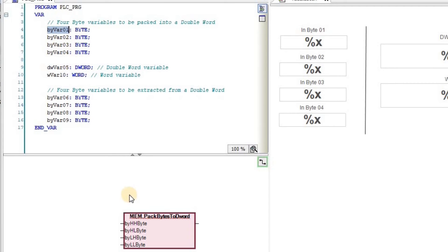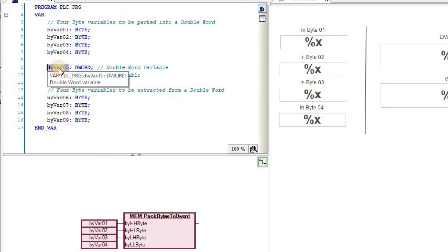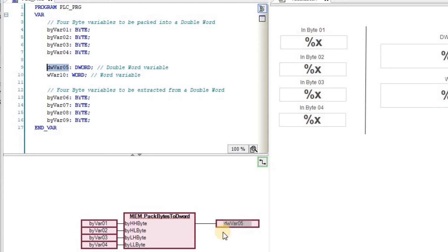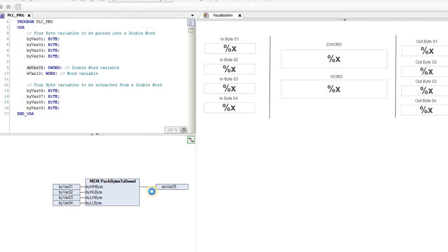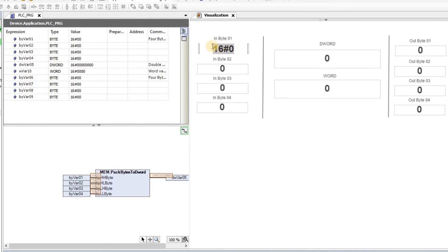Using Pack Bytes to Double Word, clicking OK shows the function name and pressing Enter reveals the four inputs along with one output. For the inputs I will use byte_var_01, 02, 03, and 04 for HH byte, HL byte, LH byte, and LL byte respectively. I drag and drop the variables from the variable declaration area into the program development area. As the output I assign double_word_var_05. Now I log in and run the code to show how these four bytes are combined.